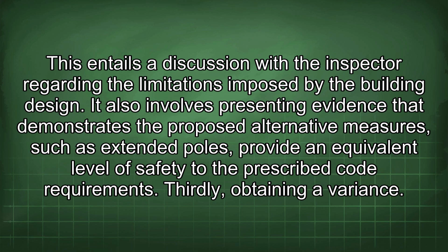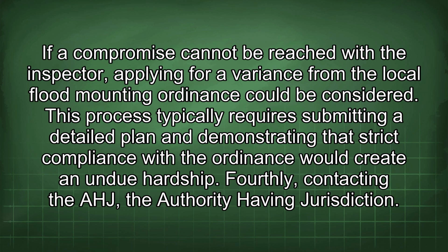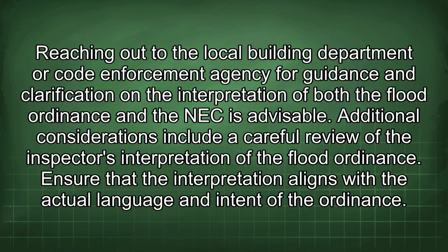Thirdly, obtaining a variance. If a compromise cannot be reached with the inspector, applying for a variance from the local flood mounting ordinance could be considered. This process typically requires submitting a detailed plan and demonstrating that strict compliance with the ordinance would create an undue hardship. Fourthly, contacting the AHJ, the authority having jurisdiction. Reaching out to the local building department or code enforcement agency for guidance and clarification on the interpretation of both the flood ordinance and the NEC is advisable.